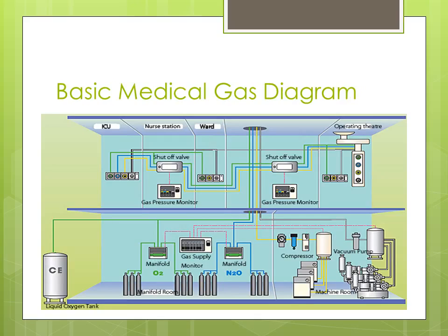So here's the room again. Okay, we got one tank. It's just a picture, but there should be a second tank. The thing about the monitor is this. Here's the gas monitor. And interestingly enough, it's in a room that appears to be with all the manifolds and all these other tanks. Is this a rated room?